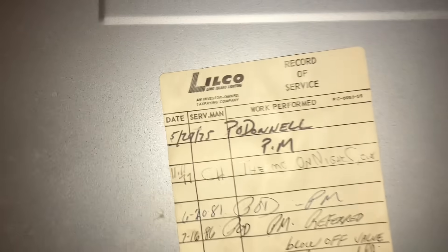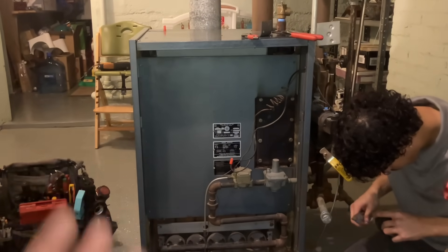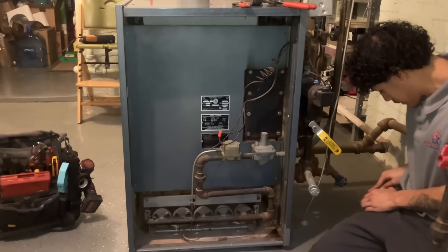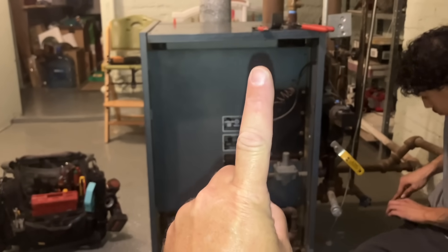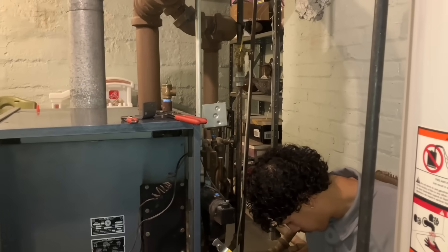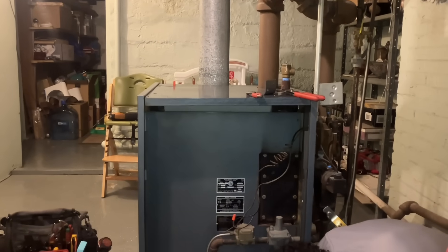It's a far cry from 50 years ago till today. But one thing that has not changed is that this Weil-McLain boiler has been providing decades of reliable service, as antiquated as it is, with literally only two safety components: one being the low-water cutoff, and two being the Pressuretrol. Insane. Absolutely insane. There's no rollout switch, there's no spill switch, there's no automatic vent damper.